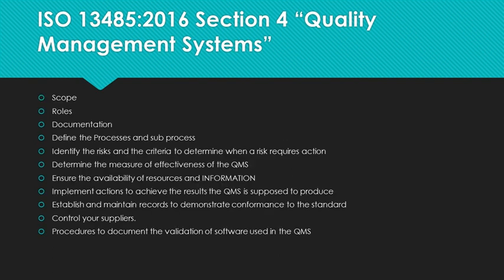Your first step in creating the quality management system is that you need to decide how your organization will handle the following requirements. The scope. What is in the QMS and what is not? Think exclusions and not applicable clauses. You also want to define the limits of the work you perform. For example, if you are servicing equipment, which OEMs do you work on? Anything you don't include will be considered outside the scope, unless you include a catch-all phrase such as "and similar devices."